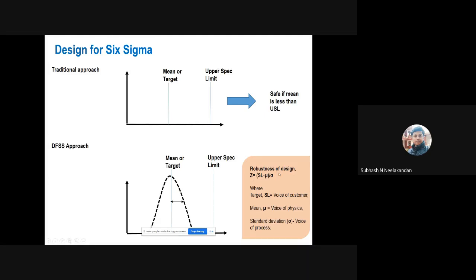and have to find out what is the robust design score of critical parameters. I'm repeating, critical parameters, not all parameters. For the critical parameters, what are the Z scores? So now the industries are following a practice that if the Z score is 6 or close to 6 or above 6, it is well and good for releasing into the market. So this is one safe criteria check which some of the companies use nowadays so that there should be minimum returns or minimum complaints from the field.